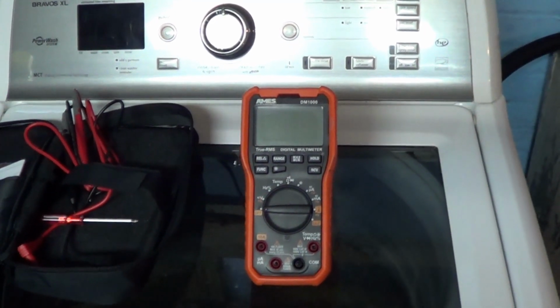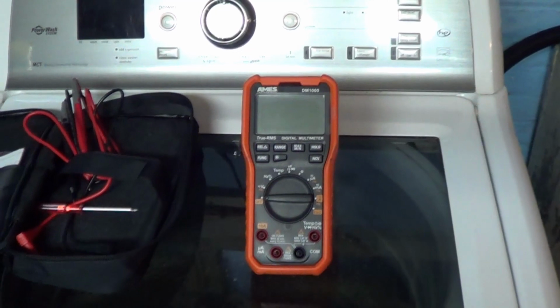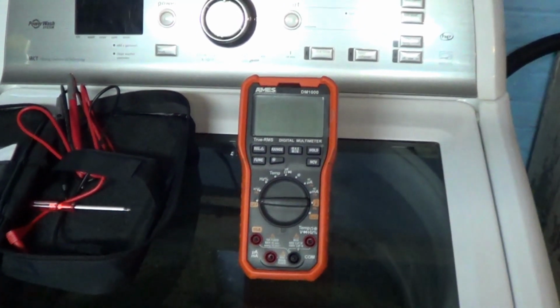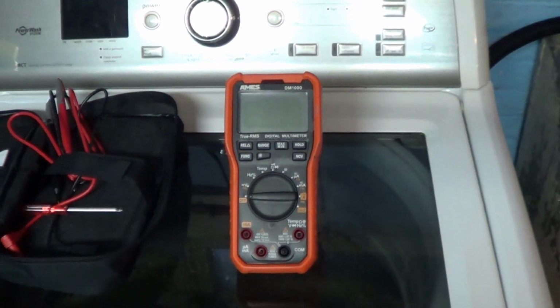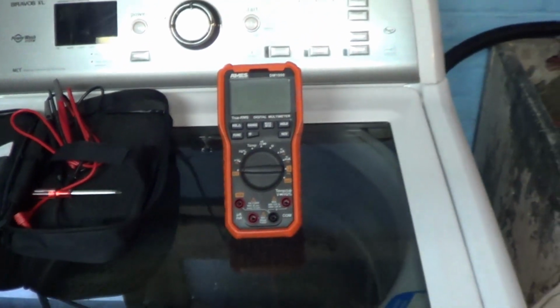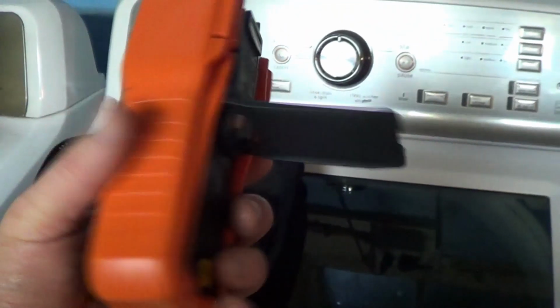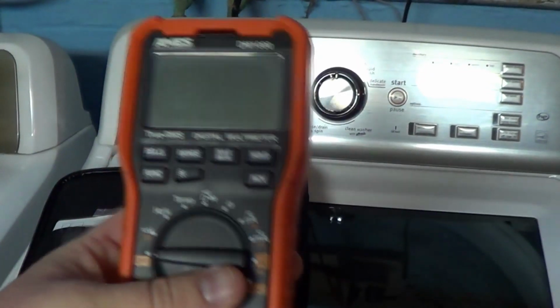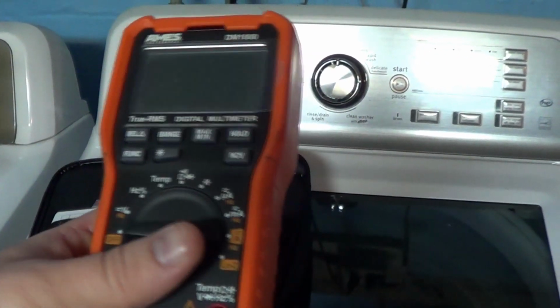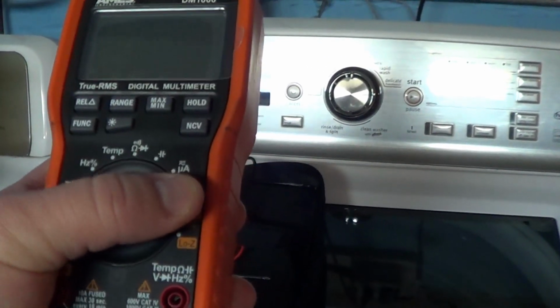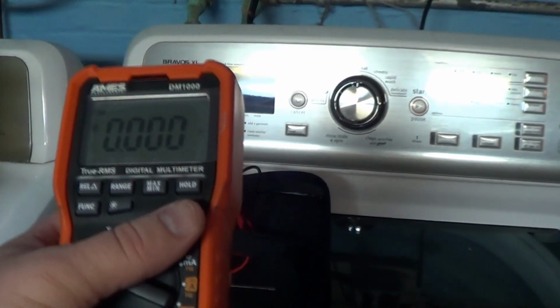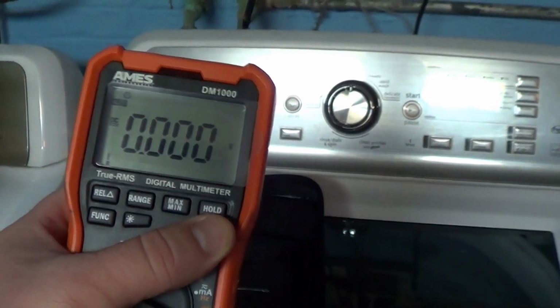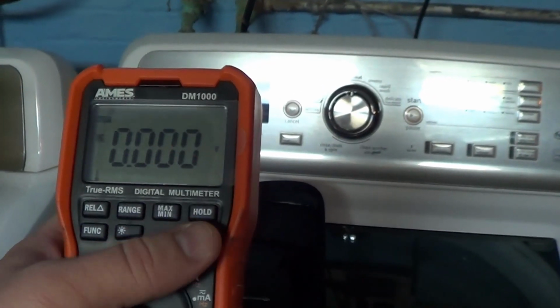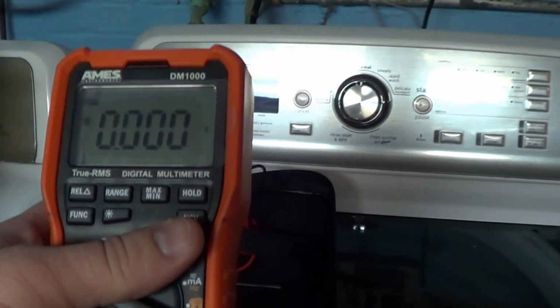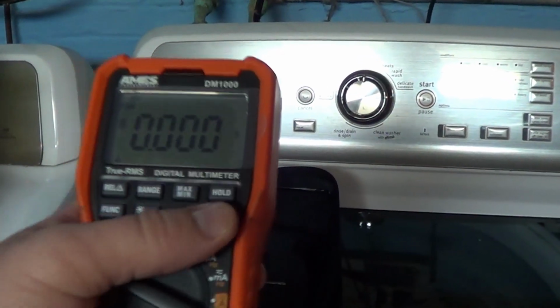I would never, ever, ever suggest that you rely solely on the non-contact voltage detection feature to ascertain whether or not there is in fact voltage present in a conductor. Some people have complained that this is pretty deaf. I would say by comparison to some of my other multimeters, it is a little bit lackluster in its capability. But if we turn it on and we hold down the button, which you have to do, it doesn't give you any indication that it's actually gone into the non-contact voltage measurement mode.